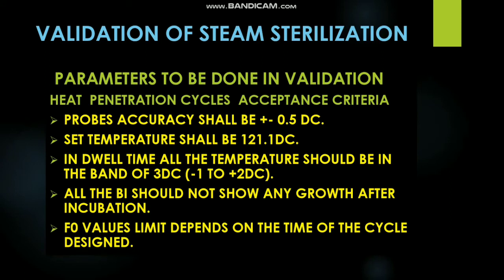Now the acceptance criteria for the heat penetration cycles. Probe accuracy shall be plus minus 0.5 degree centigrade. The set temperature shall be 121.1 degree centigrade. In the dwell time, all the temperatures should be in a band of 3 degree centigrade, that is -1 to +2 degree centigrade of the set temperature.